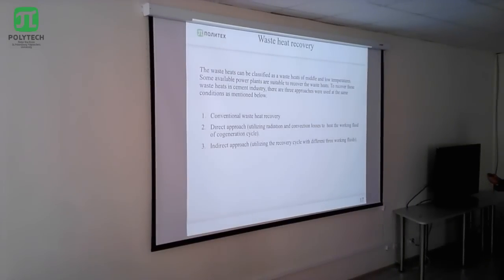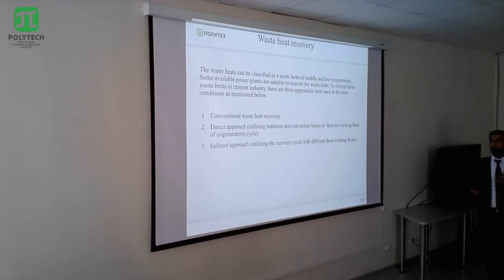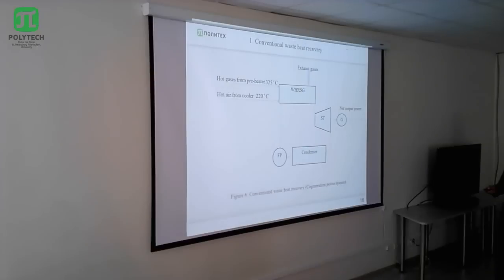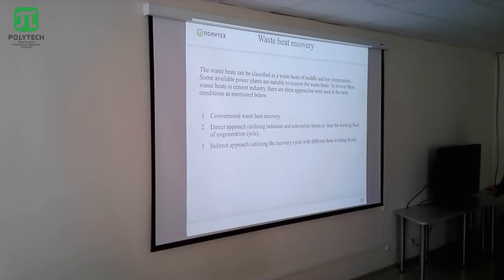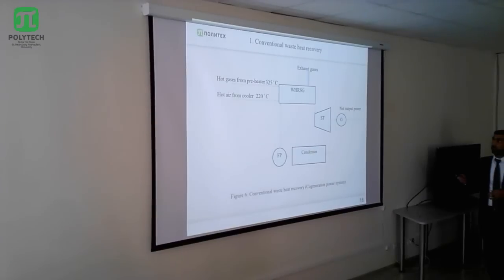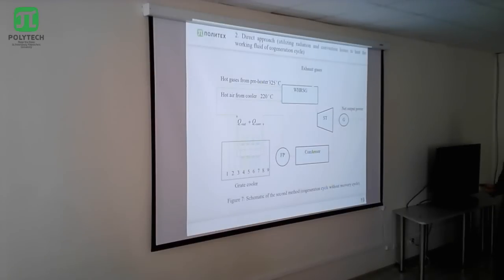The second objective is waste heat recovery. As mentioned before, to calculate waste heat recovery we have three approaches: conventional, direct, and indirect. This is the conventional waste heat recovery approach. This simple Rankine cycle consists of the waste heat recovery steam generator, steam turbine, and generator to produce electricity, along with a condenser and feed pump. This represents the heat losses from the clinker cooler, and the working fluid is water. The second approach is the direct approach.